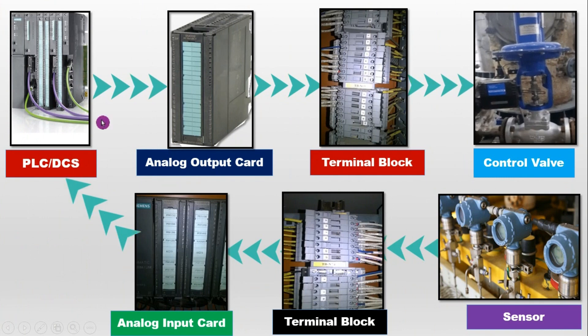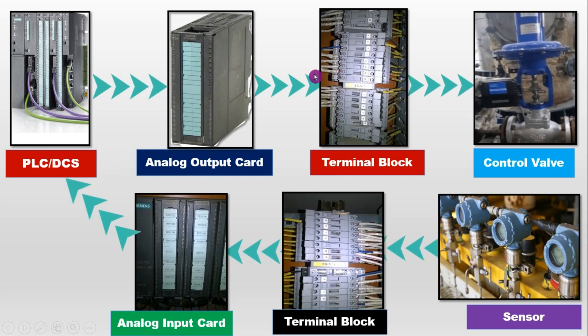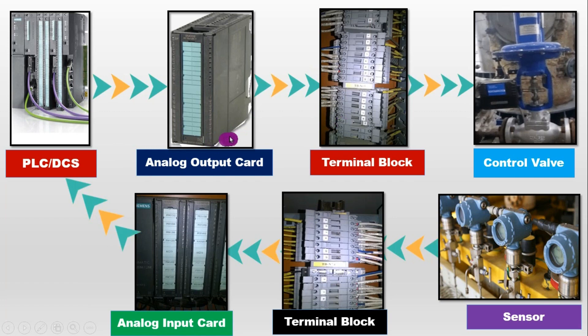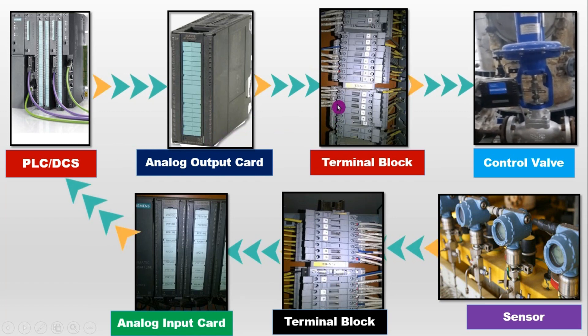The signal to operate a control valve is sent to the terminal block in PLC DCS panel via analog output card or analog output module. This signal is 4 to 20 mA signal and provided to positioner. Then positioner positions the control valve according to the signal.